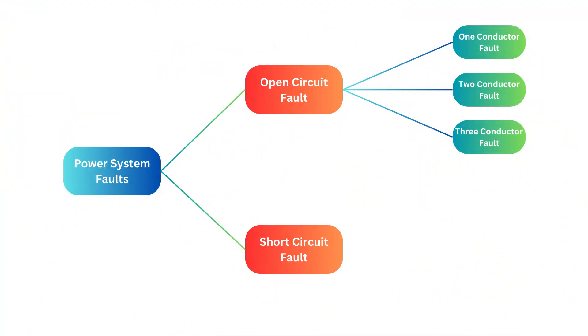Open circuit faults mainly occur due to the failure of one or more conductors. Since these faults occur in series with the line, they are also called series faults. Open circuit faults affect the reliability of the system and are classified into one conductor open fault, two conductors open fault, and three conductors open fault.